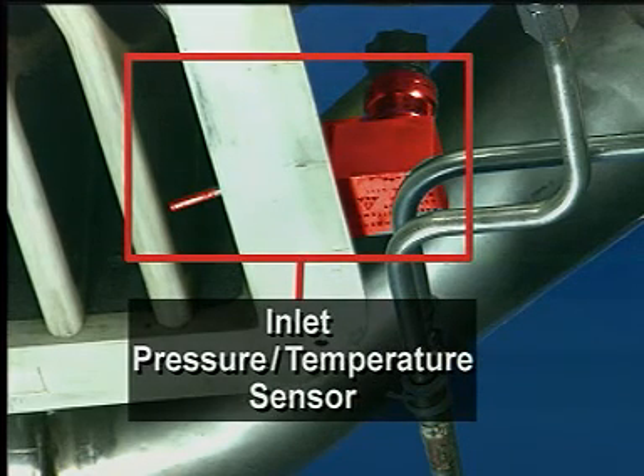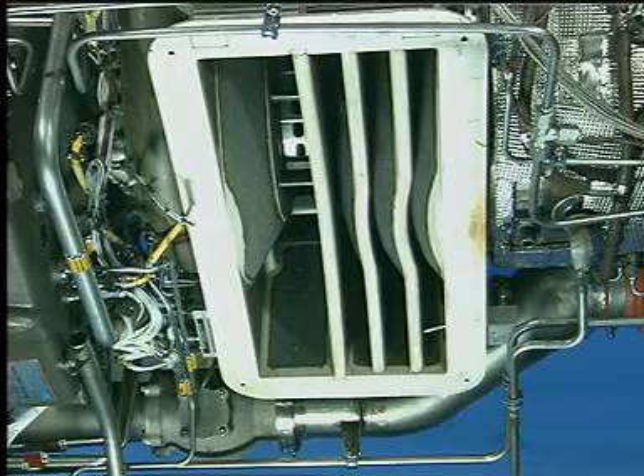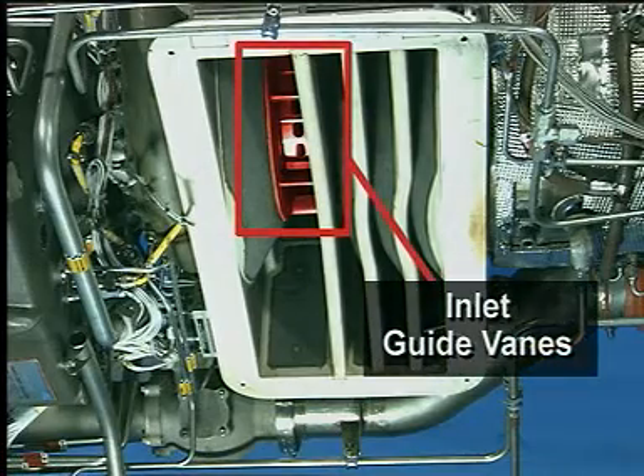The airflow is monitored by the load compressor inlet pressure temperature sensor installed on the rear of the air inlet plenum near the 3 o'clock position. The data is used for fuel metering control. The airflow to the load compressor is controlled by a row of internal inlet guide vanes.